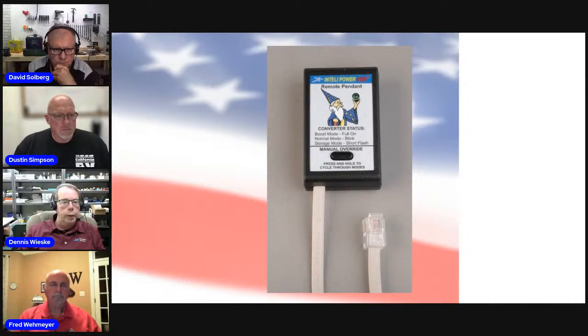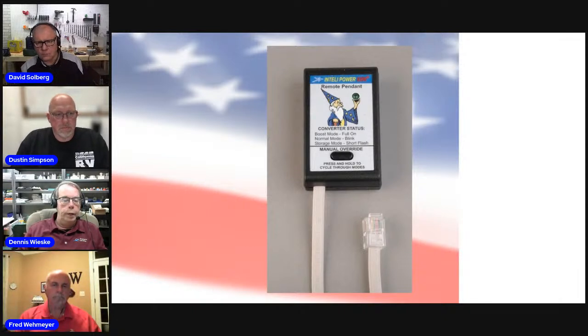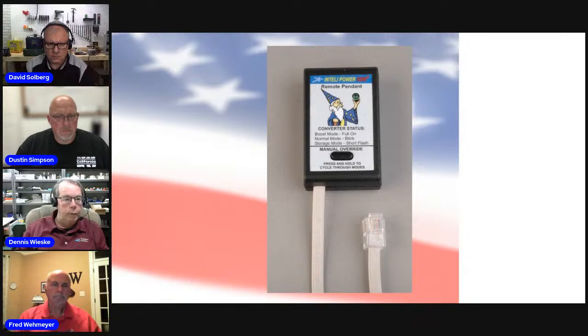Really, its only function as far as the LED is to tell you what mode the charger is in. This still operates even though you remove shore power, because the charge wizard in our chargers is in the output circuit of the charger itself, so it sees the battery voltage directly from the battery. As long as that voltage is above 5 volts—the standard operating voltage for the computer chip that runs the charge wizard—it will maintain function and monitor that battery voltage. Once the voltage drops below the threshold, it triggers the converter into boost mode and continues to trigger that mode. When you plug in, away you go, charging at 14.4. That's a good indication: if you see that light up, it means your battery got below 50%, down below 11.9 volts, and you should have already had your rig plugged in.